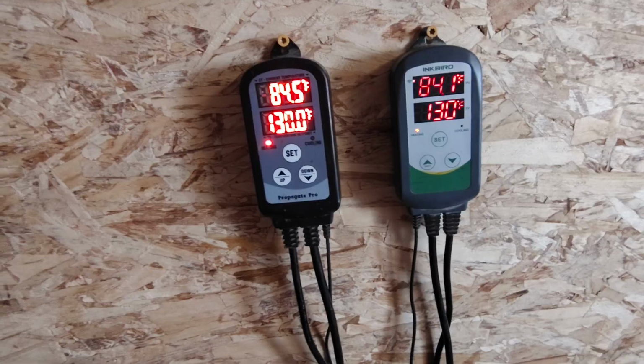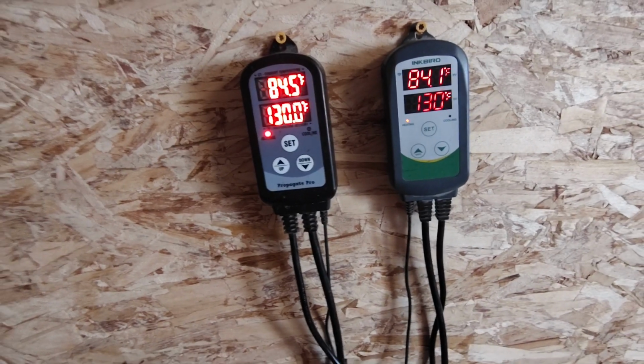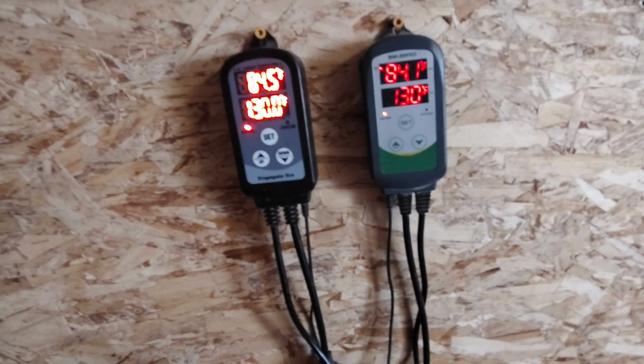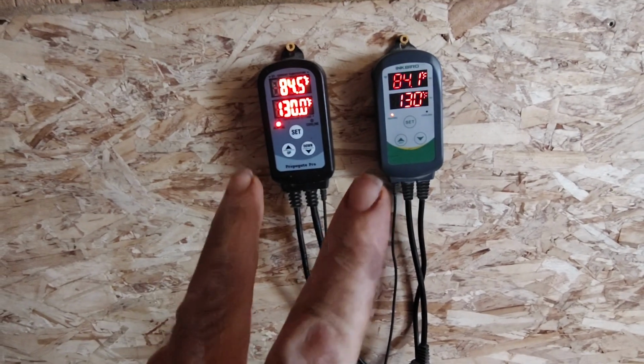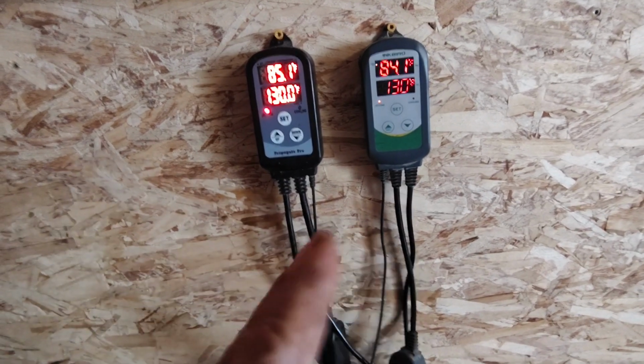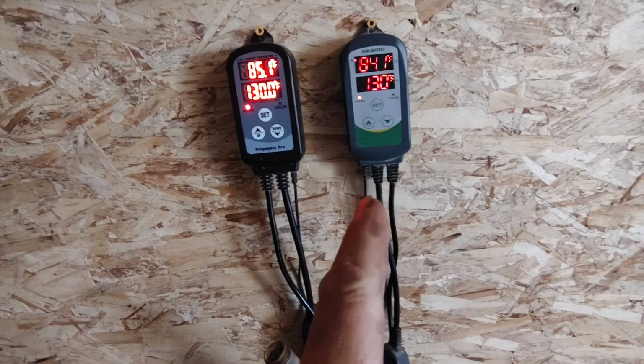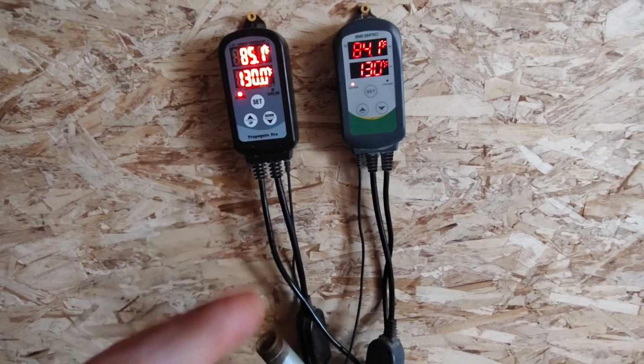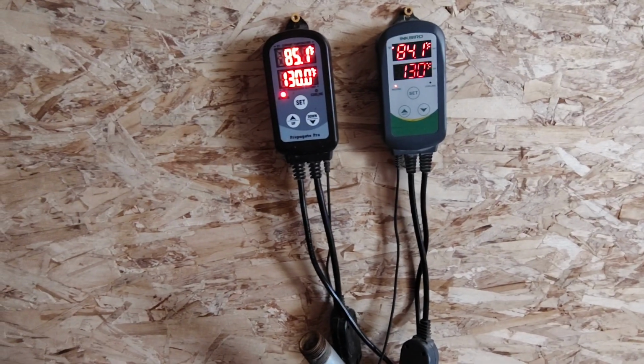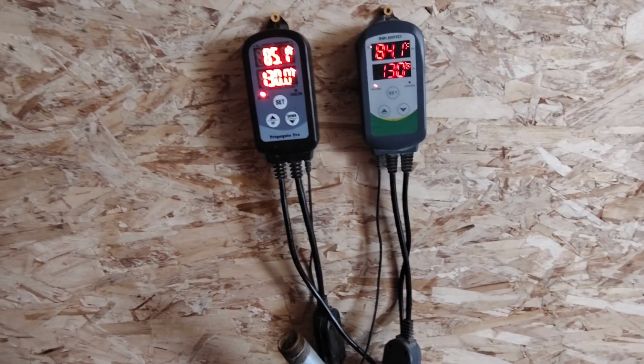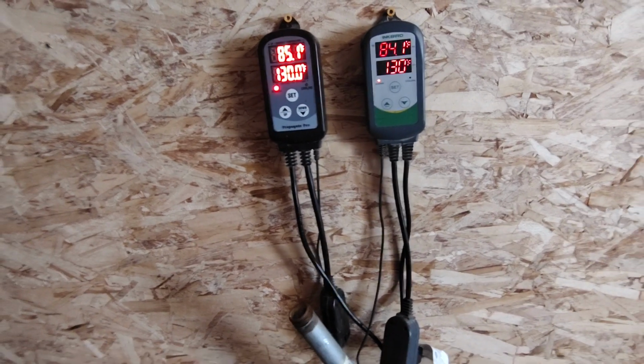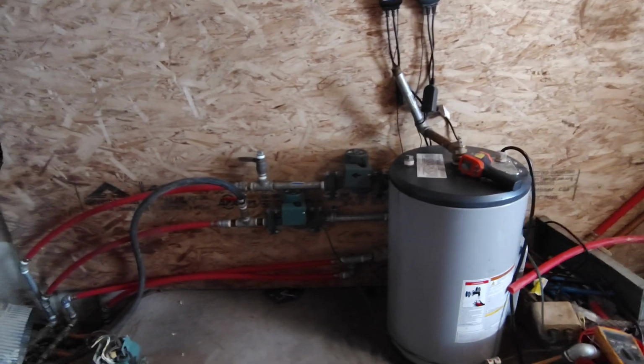It'll get there as soon as the floors heat up. Probably about 92 degrees is where the temperatures will slowly separate, where the returning temperature won't be as high as the outgoing temperature. But that's just as it approaches saturation in the concrete. But then you can always raise the temperature in the tank, and those numbers will adjust again.